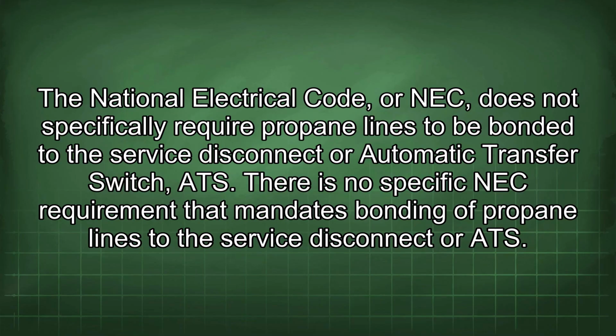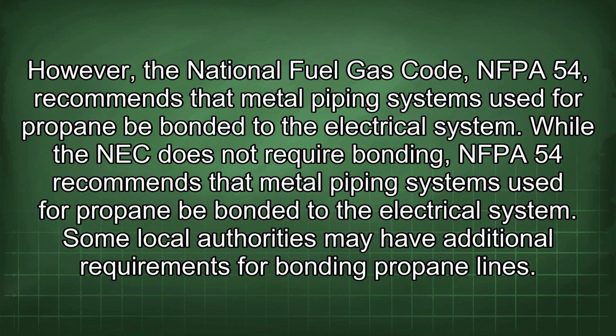The National Electrical Code, or NEC, does not specifically require propane lines to be bonded to the service disconnect or automatic transfer switch, ATS. There is no specific NEC requirement that mandates bonding of propane lines to the service disconnect or ATS. However, the National Fuel Gas Code, NFPA 54, recommends that metal piping systems used for propane be bonded to the electrical system. While the NEC does not require bonding, NFPA 54 recommends that metal piping systems used for propane be bonded to the electrical system.